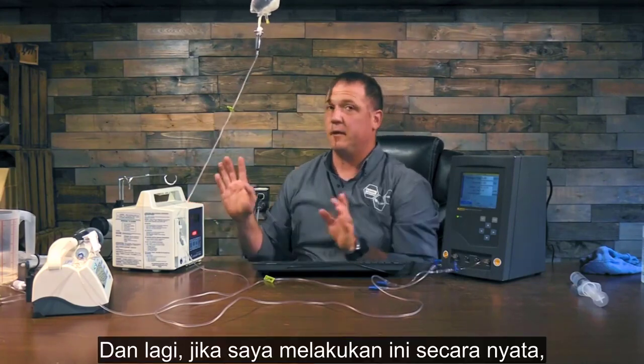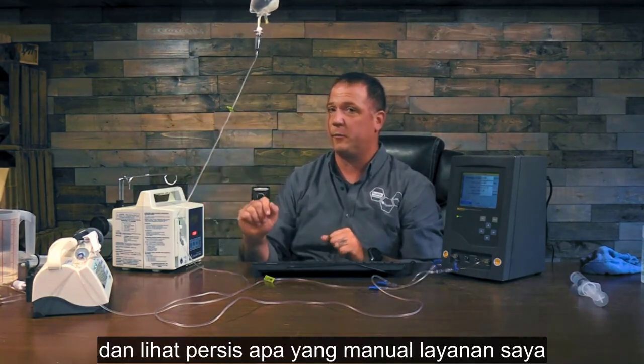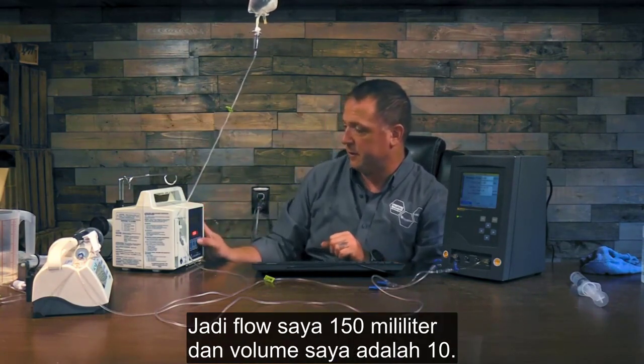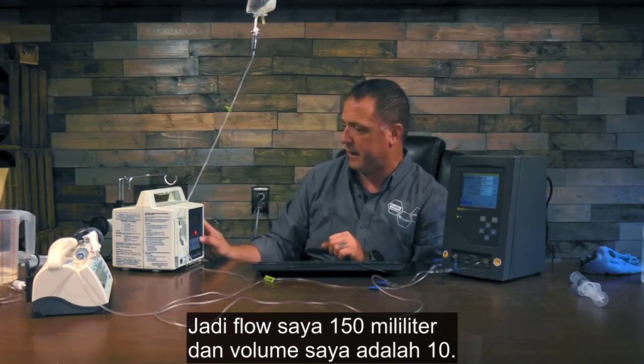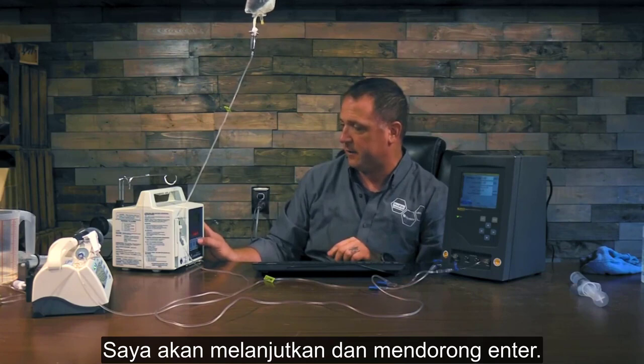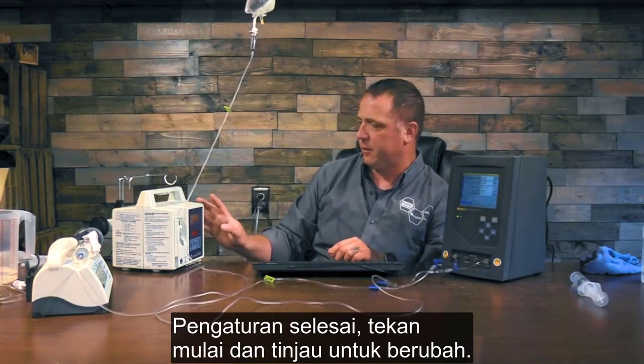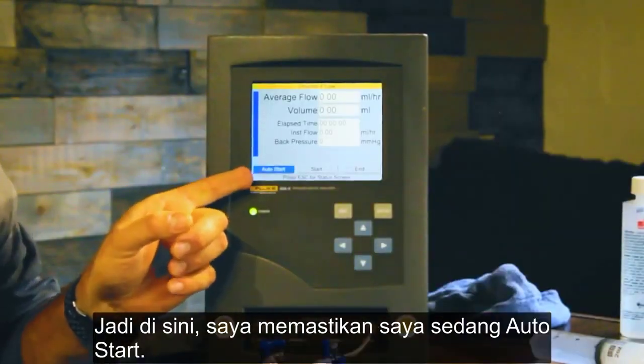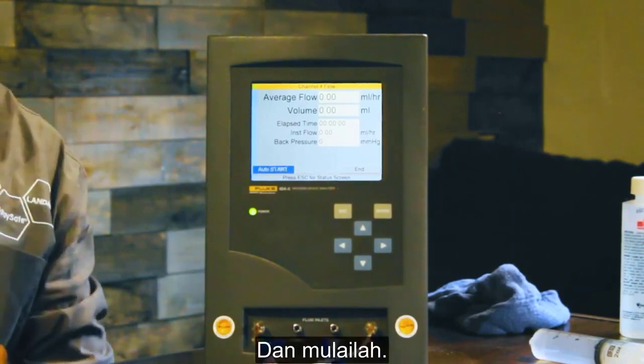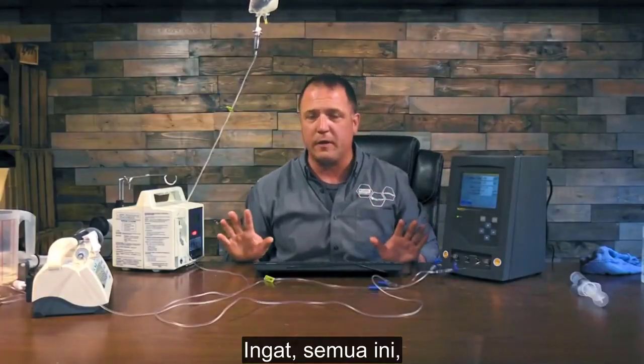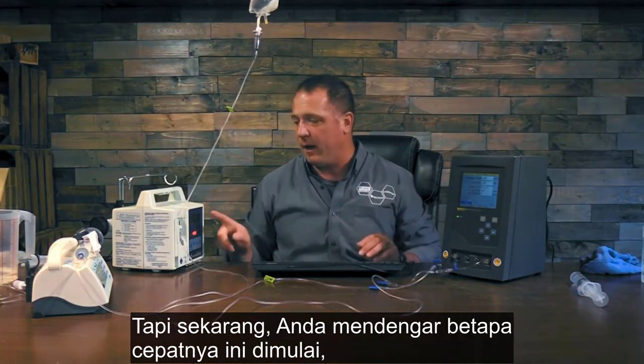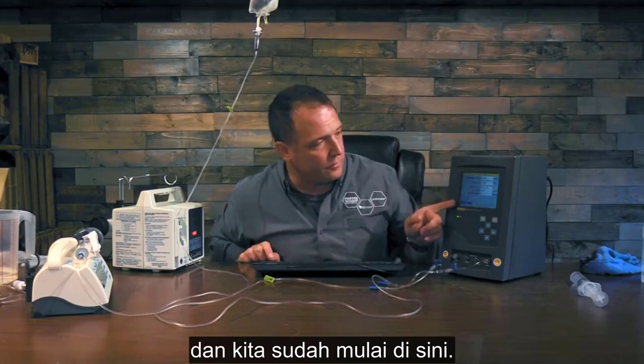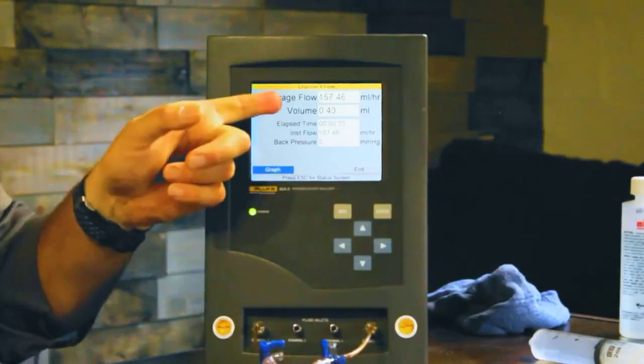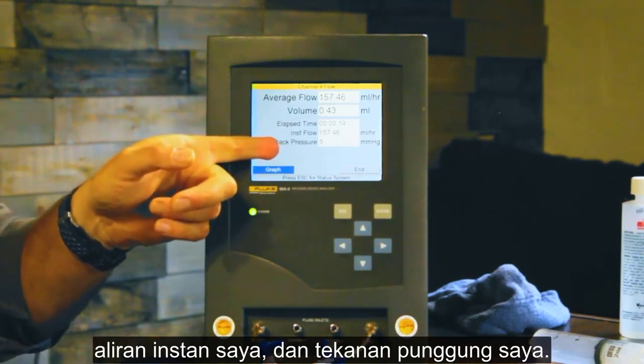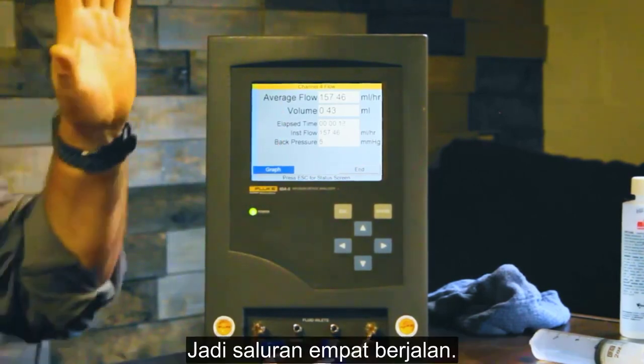And again, if I was doing this for real, I'd have my service manual and see exactly what my service manual wants me to set it to. So my rate's 150 milliliters and my volume is 10, because that's what we set in there. I'm going to go ahead and push enter. No secondary. Settings complete, press start or review to change. So here I make sure I'm on auto start and start. Remember, all this I should go to my service manual and pull up my data. But now you heard how quick this started and we're already started here. There's my average flow, my volume, my instant flow, my back pressure. So channel 4 is running.